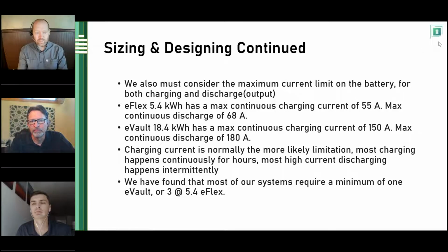I think I mentioned already, charging current is more likely where you're going to run into the limitation, more so than the loads. Most of your loads that have high current are like a lock rotor amp, for a compressor, a well pump, a motor, things like that. They typically last for milliseconds, so not as critical.